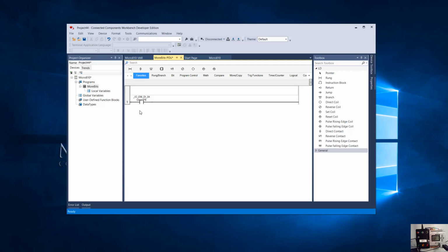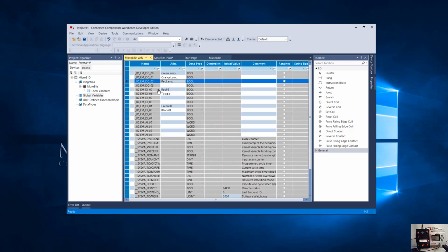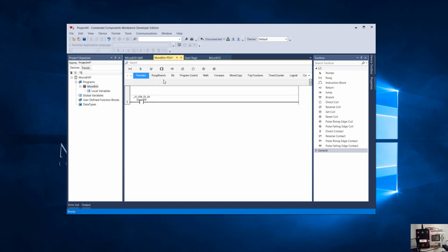Okay, so let's talk a little bit more, just reviewing what we did on Wednesday again, what this instruction means. There are two things you need to understand to make sure you're using these input style contacts correctly. The first is that there is a hardware true or untrue. So if there is a voltage present on input 4, then the input, we would say, is energized. The input would be a 1. If we came back and looked at that input while it was connected, it would have a check mark under that physical that we looked at before.